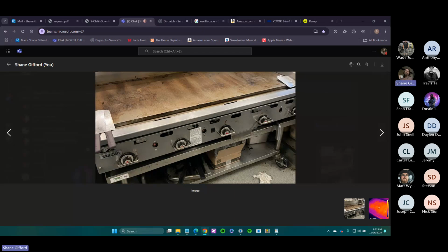So like on this, I think it might be the griddle at Five Guys to the left of the fryers. That's exactly how you calibrate those. You have to hold on to the knob, pop that little front off, release the set screw, and then don't take it all the way off unless you have to, because sometimes they can be a pain in the butt to put back in, or there's a little clip on the inside of the knob that you dropped and you didn't realize you dropped it. Then you're screwed.